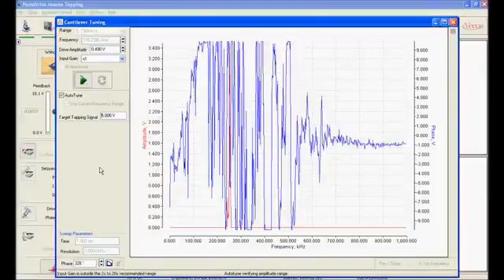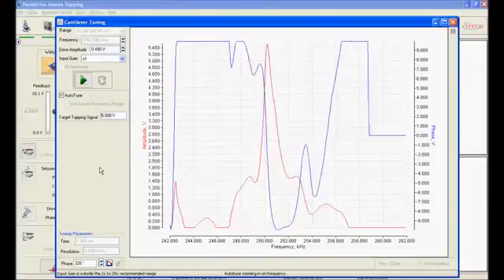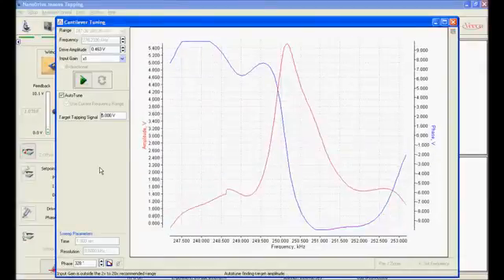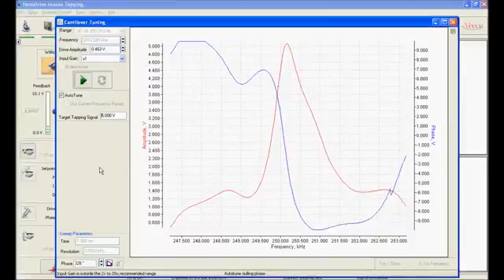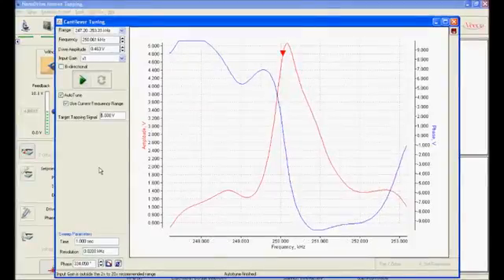These cantilevers should have a frequency around 300 kHz, and if your frequency is too far off, this could indicate a problem with the cantilever. Take note of this frequency profile. This is a new tip, and a good tip should have a profile similar to this. If the profile looks very different, you have a bad tip.